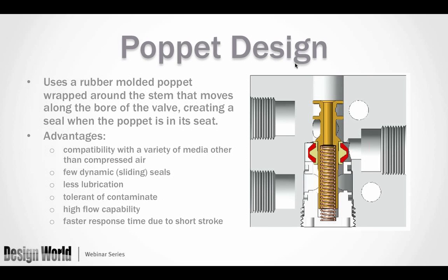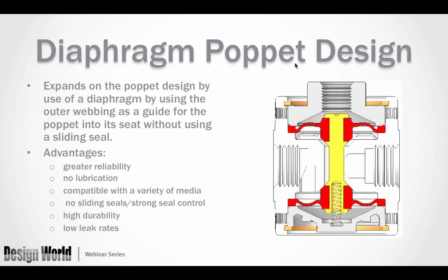A variation on the poppet is the diaphragm poppet design, which adds a diaphragm to help hold the poppet in the proper position via webbing. It's a very reliable type of valve that doesn't require lubricant because there are no sliding seals. It's capable of handling many different media, depending on the seal and diaphragm materials. It's a very durable valve with typically very low leakage, and often provides isolation between the media and the actuator, whether air-piloted or electrically actuated.